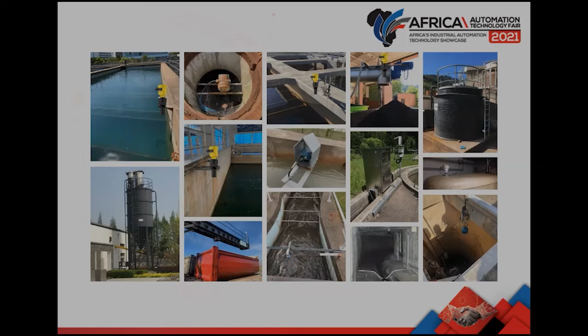A sound wave is transmitted to the application, reflects back, and there's a number of factors that affect the sound wave from the ultrasonic level transmitter. If we look at a few of these factors that exist in some applications: pressure factors, maybe pressure vessels, sometimes processes run under vacuum, there could be certain gases and fumes present in the measurement, high temperatures, steam, wind, fog, humidity, rain. So if we look at these factors, ultrasonic technology is normally affected negatively, which might cause maintenance issues.